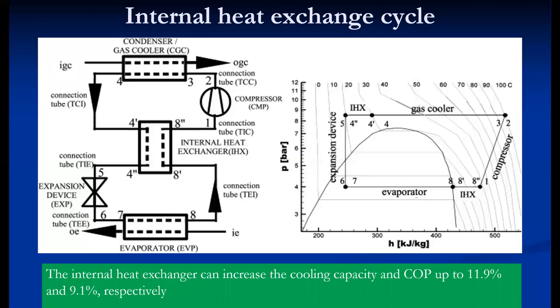The first modification is the use of an internal heat exchanger in the cycle. In the transcritical cycle, if we use an internal heat exchanger, we can shift point 4. In a conventional transcritical cycle expanding without an internal heat exchanger, the point is somewhere here, but with the internal heat exchanger, the point is shifted to point number 6. Because of this shifting, there is almost 9 to 10 percent increase in COP. This is the internal heat exchanger cycle, that is the CO2 cycle.